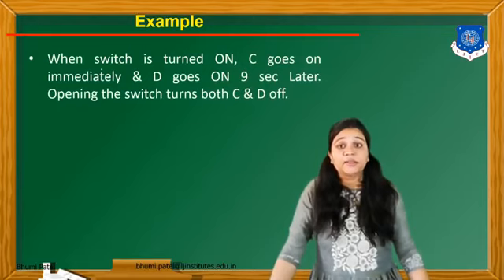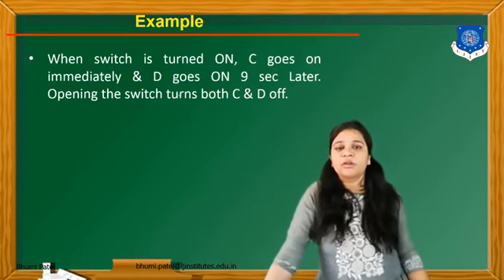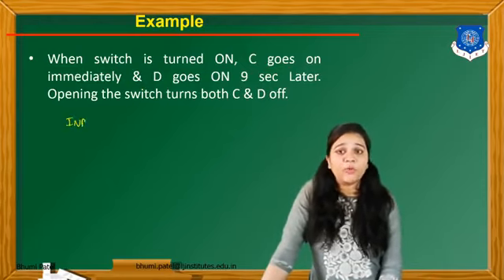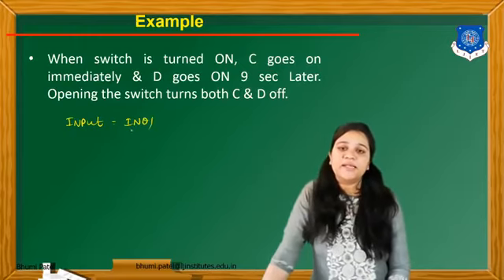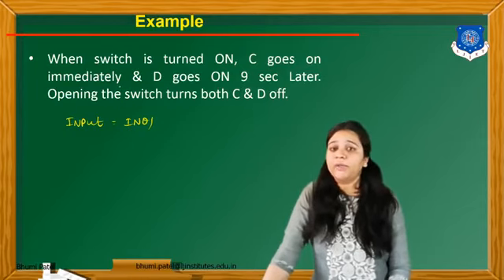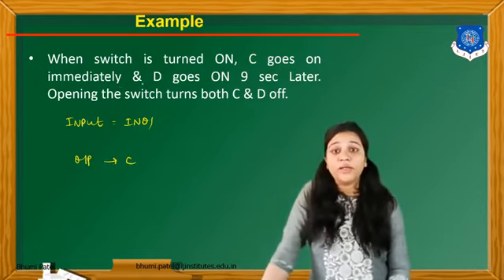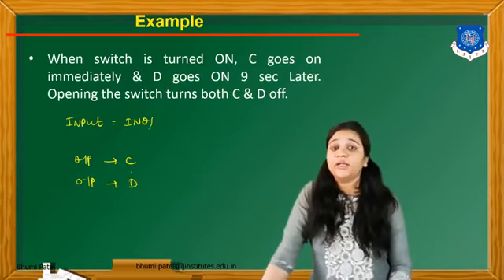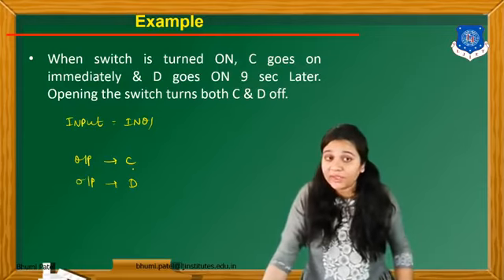The next example: when a switch is turned on, C goes on immediately and D goes on 9 seconds later. Opening the switch turns both C and D off. So first of all we write down how many inputs and outputs there are. We take one input switch, named IN01. C goes on immediately — so our first output is C. D goes on 9 seconds later — so our second output is D. For D we use the timer on delay with a preset value of 9 seconds.